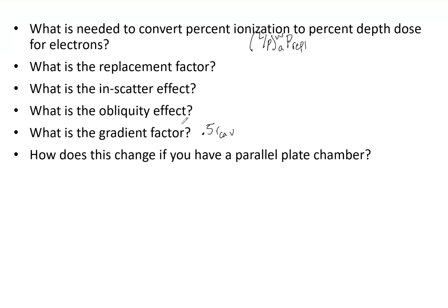Now how does all this change if we have a parallel plate chamber? Well, there's a P_fluence correction factor as well that we didn't discuss here, but there is one. There is also that P_gradient, but those can be ignored because we are working with a parallel plate chamber.